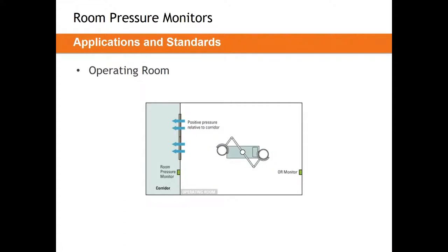For a standard operating room with a single entrance, applying the room pressure monitor is extremely simple. The room pressure sensor should go above the doorway, with the room pressure monitor to either side of that door to allow employees to know what's going on in that room before they enter.